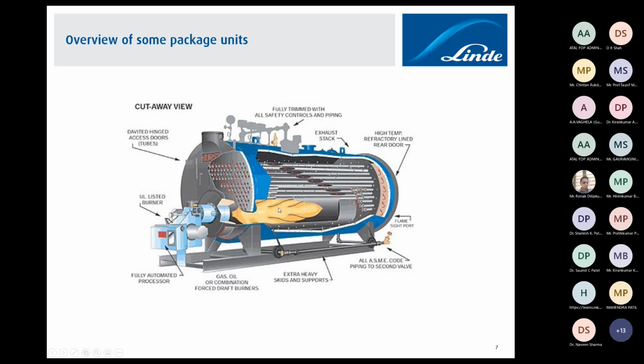So heat is transferred through the furnace wall to the surroundings, where water is filled up on the external part of the tubes. In the tubes, all the flue gases travel in a two or three pass. Here the first pass is the furnace. On the back side, a refractory lined door is there. So to conserve the heat, it goes to the second pass, and again it comes out as a third pass, and you have exhaust stacks somewhere mounted here.